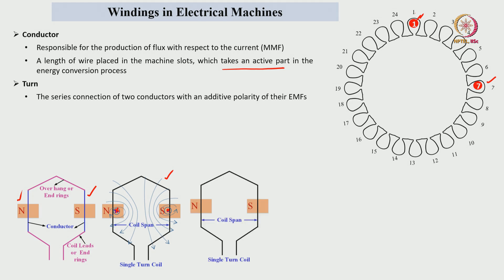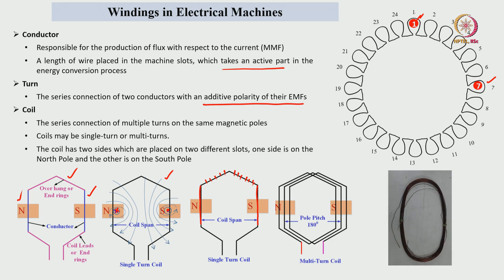A turn is nothing but a combination of two conductors with additive polarity of their EMFs. These two conductors are connected with an overhang — the pink color one is the overhang — and this configuration has only one turn. A coil consists of n number of turns, all connected in series fashion. A coil has two coil sides which are placed in two different slots — one coil side is placed at the north pole side and the other at the south pole side. The physical coil has two ends: one is the starting end and the other is the ending end.